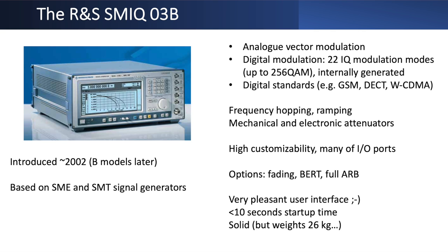So you can use control lists, and I'll show a little bit about that later, generating all types of sync and trigger signals within what you want to do. And you really have a crazy number of IO ports. I think there's something like 34 IO ports in terms of triggering and syncing and that type of thing, not counting the normal serial ports and the IEEE command port. So it's quite amazing how well you can use this. And from this you can also see that this was not only designed to be used in R&D, but also in production environments where these units were used for continuous testing. So some of them have millions and millions of usages of the relays and the attenuators in that context.